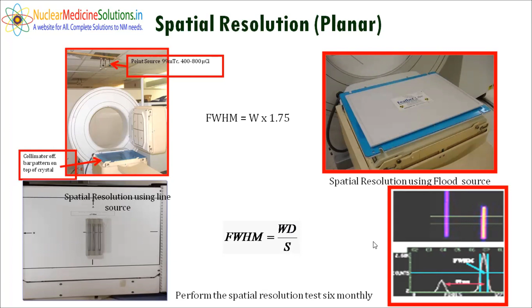And this is S, and this is D, the distance between these two sources. By knowing these two things, it will give you D by S, which gives you the pixel size, and then you multiply this pixel size with these numbers. W is the number of pixels between these two points, where we take the full width at half maximum of the photo peaks. So it will give you the FWHM of that gamma camera.